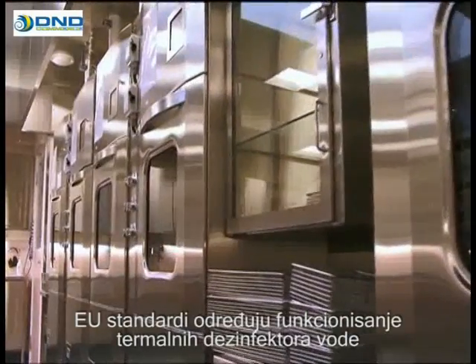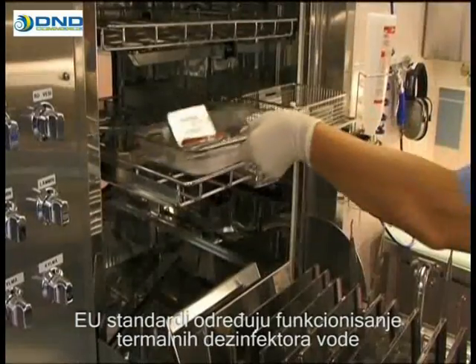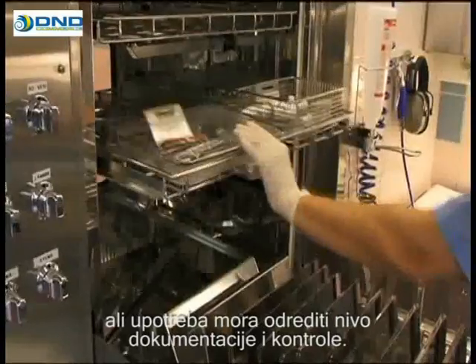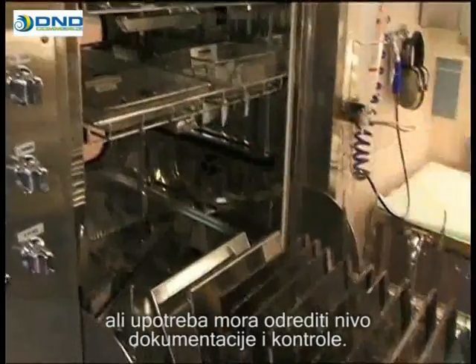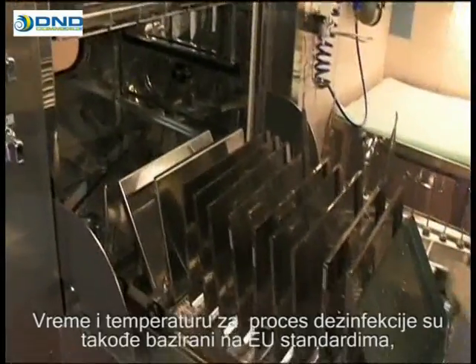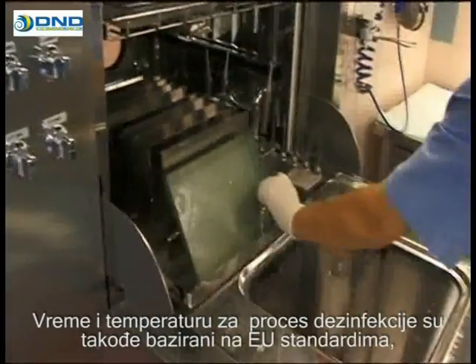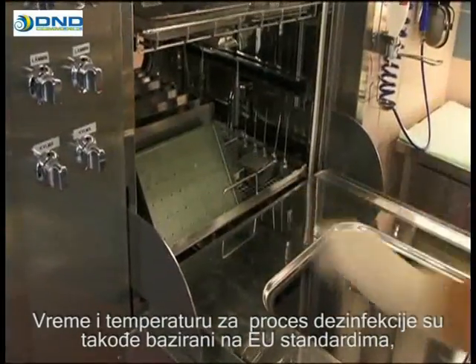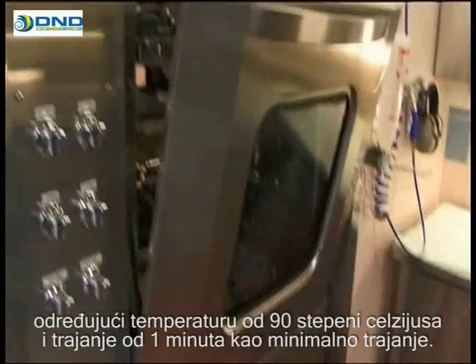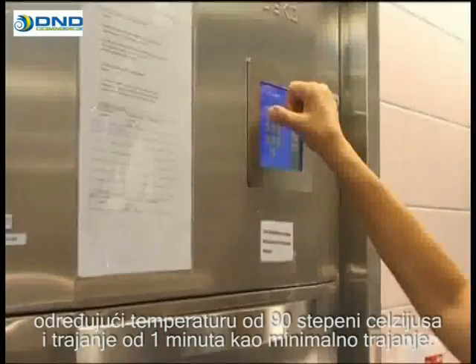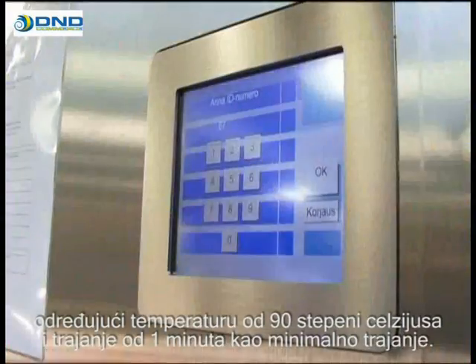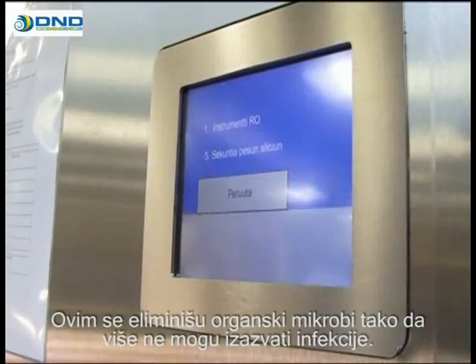EU standards determine the functions of washer thermal disinfectors, but the user must define the level of documentation and monitoring used. The time and temperature for the disinfection process are also based on the EU standard, establishing a temperature of 90 degrees Celsius and a duration of 1 minute as the minimum norm. This eliminates organic microbes so that they are no longer able to cause infections.